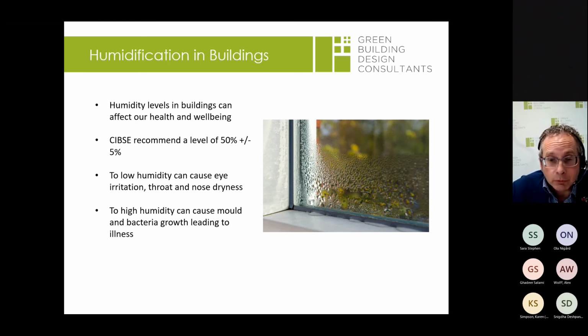If the humidity in the building then becomes very, very high, and if for whatever reason there's not a lot of heat in the building and we're bringing a lot of air in externally at 90% humidity, you often potentially see condensation can form on cold surfaces.